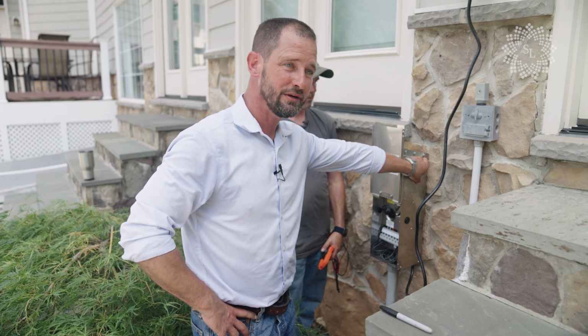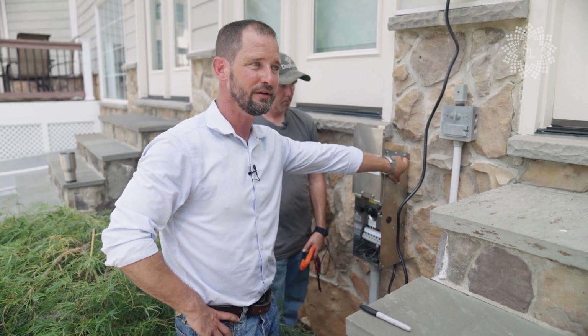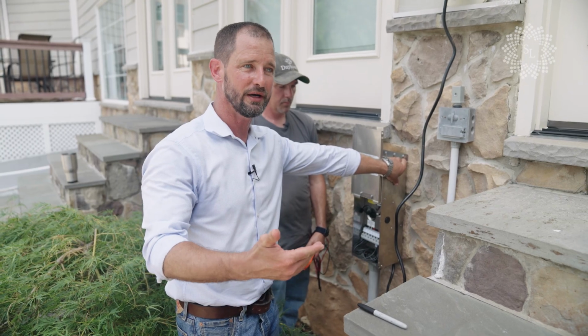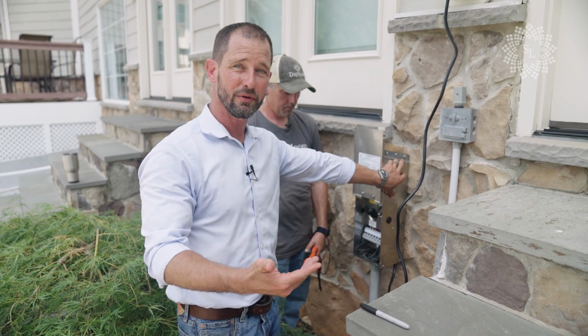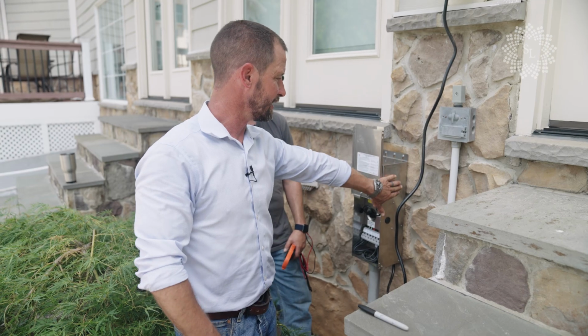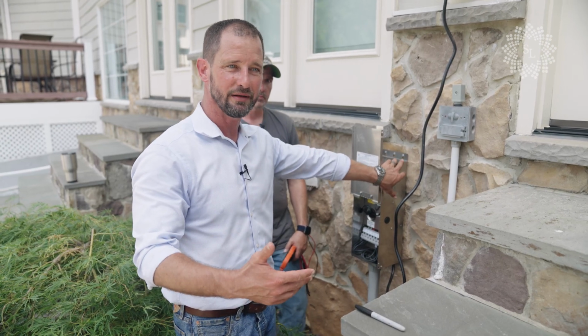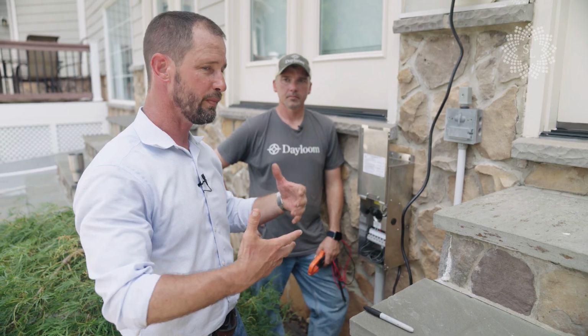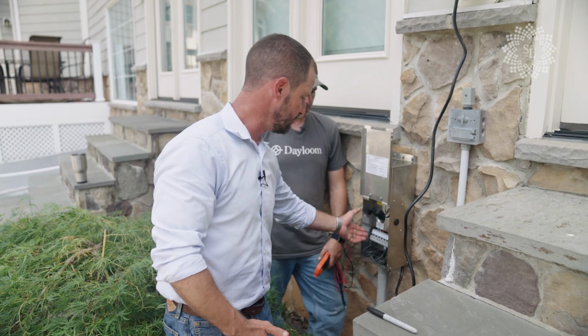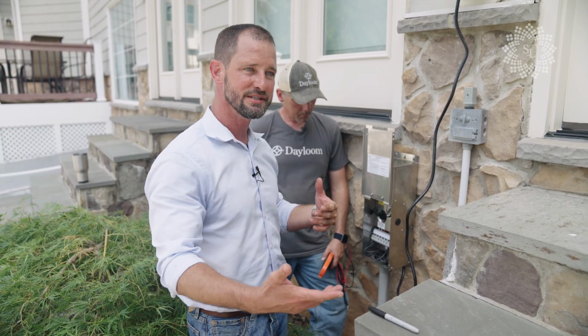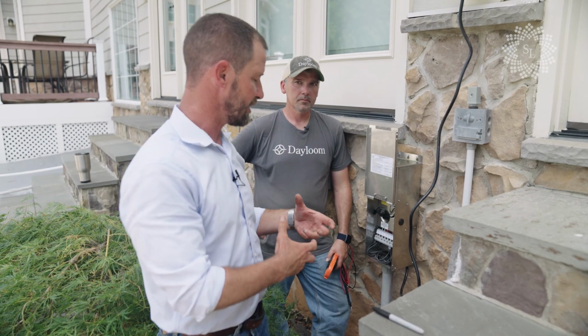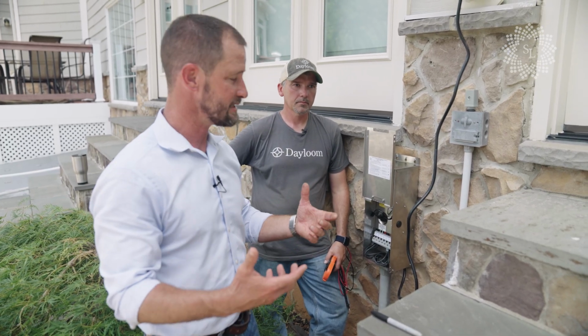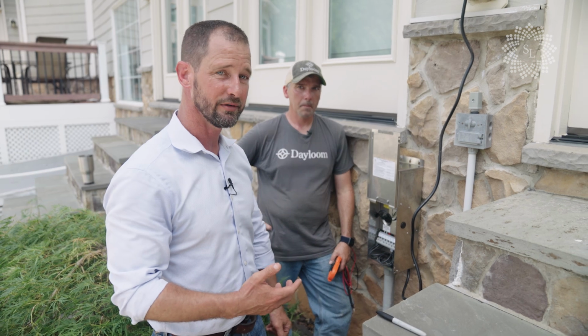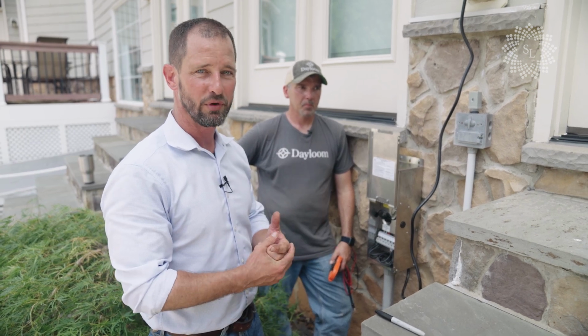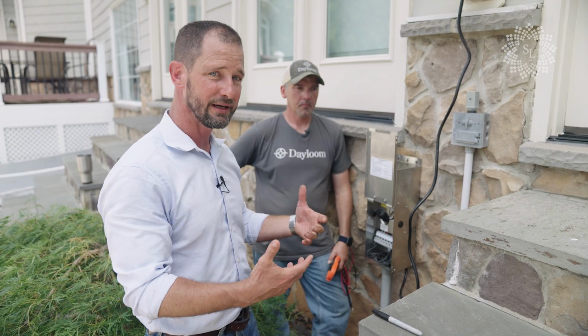These transformers, just to let you know, sometimes you get a customer that panics. They're UL tested. Basically every transformer out there is UL tested to run at 193 degrees Fahrenheit, which is hot. I typically like to keep them under like 140, and the way to do that is just overpower, have a bigger transformer, and not put too much on the commons. When you go longer distance, you're putting more pressure on the wire, and that means more resistance, and that could actually cause the amperage to go up and cause more heat on the transformer. So those are all things we look at on the original design when we're planning everything out.